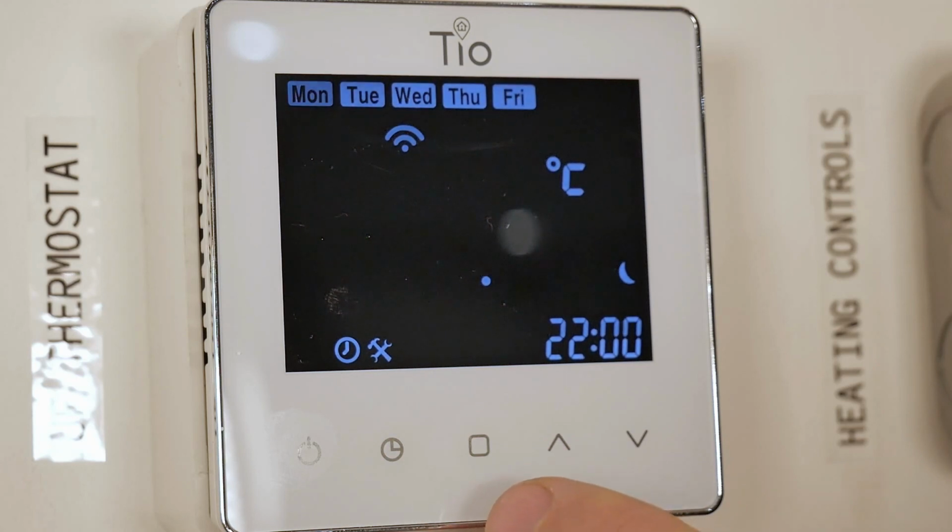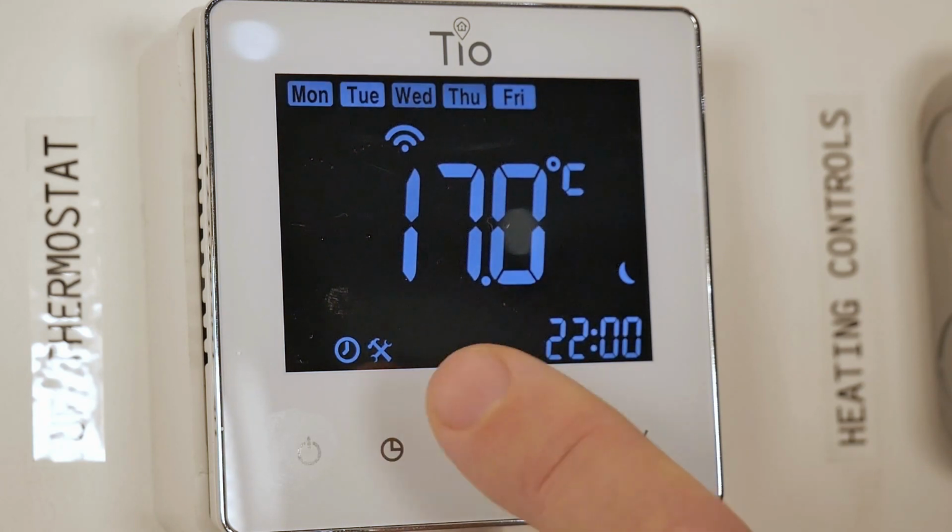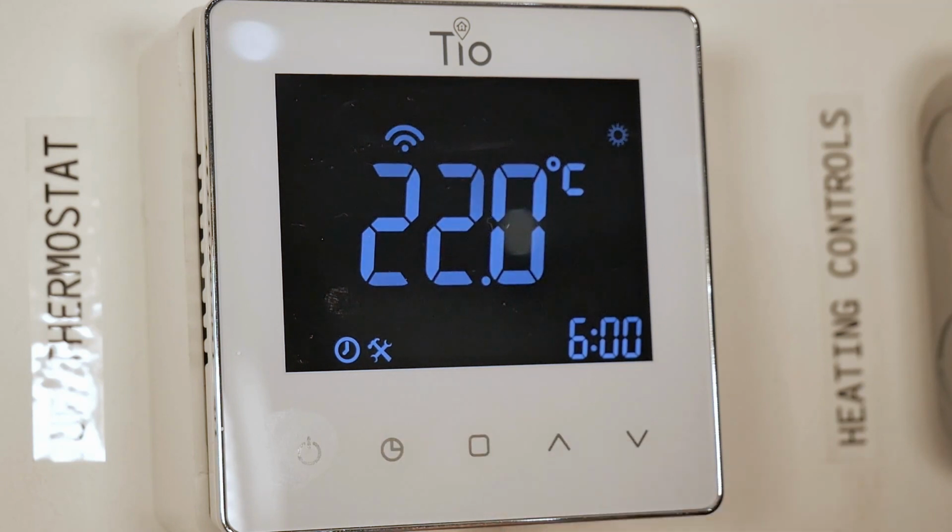Between 3 or 4 degrees, you want your occupied and unoccupied set point temperatures varying between. We don't really want, if you're using an air source heat pump, the underfloor to be off for any length period of time due to having to work harder for recovery.